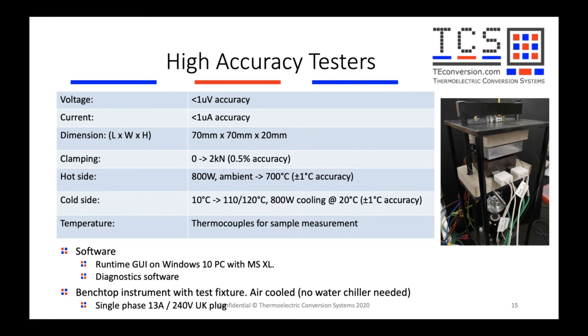The system uses thermocouples, but we can switch to using RTDs if that's more in line with what you're looking for. Again, this is on a system that uses a PC with Excel outputs and diagnostic software. This is seen as a benchtop instrument, again with no separate vapor compression unit needed. We use thermoelectric coolers to provide the cooling for the cold side.